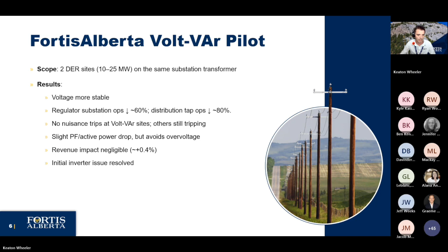Now, we did have some ratchet problems originally when we first started this, but that was boiled down to an inverter malfunction, which caused the reactive power absorption to go well beyond 90% power factor leading. So that's where the ratchet issue happened. But once that was corrected, we didn't experience any more ratchet problems. Yeah, that's from the pilot.